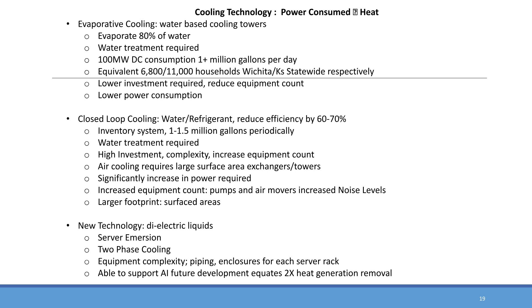Cooling requirements, real quick, final considerations. Computing, I just talked about it. On the top, as you move down, they become more energy intensive. That means more heat, which means more water. For cooling selection, if you use just water, 100 megawatts will use 1 million gallons a day. But if you do closed loop, now you've got to put it all through the air. You've got to double or more the number of pieces of equipment. The power goes up 10 to 15%, and you get a lot of noise. So there's always a trade-off, and that's what they're dealing with.